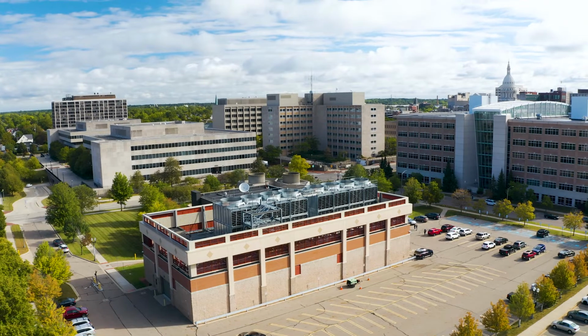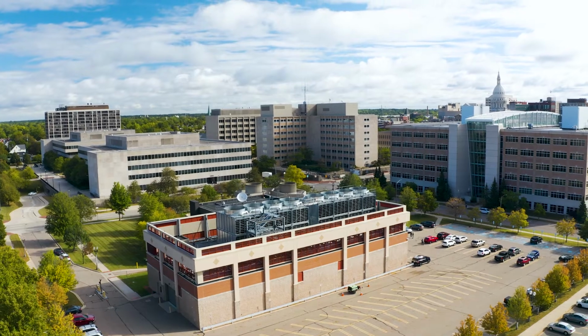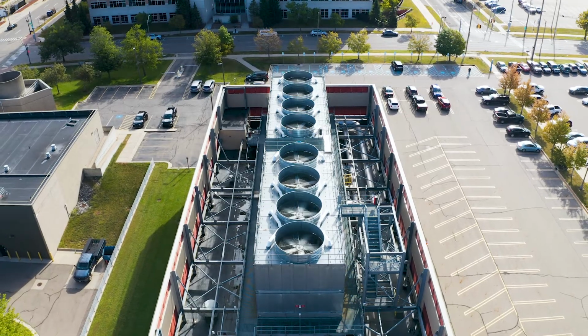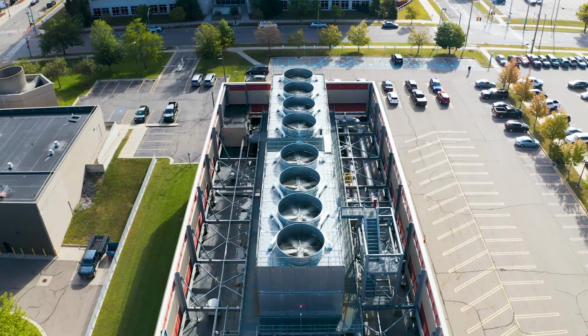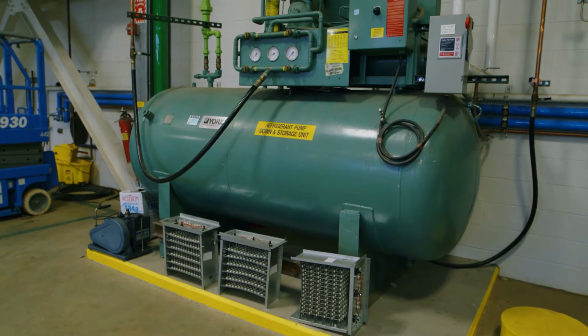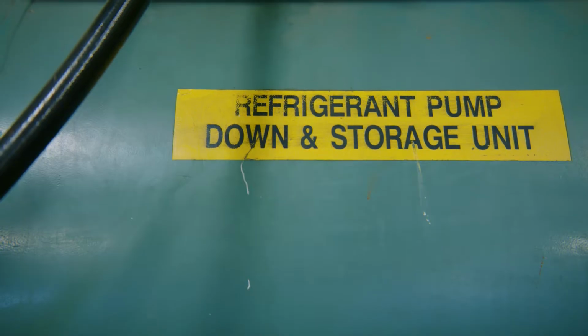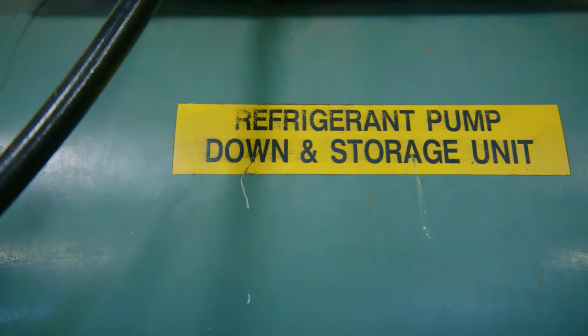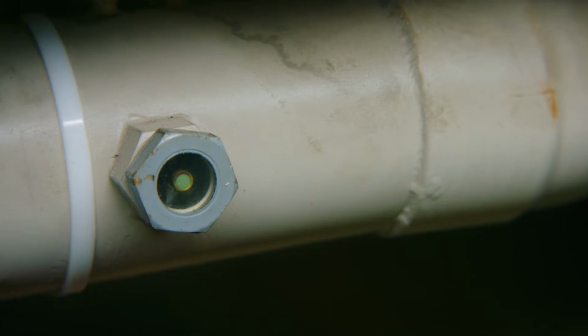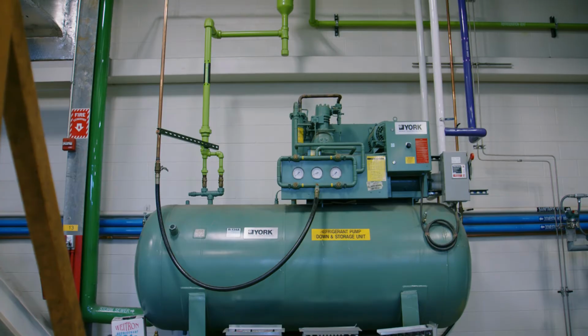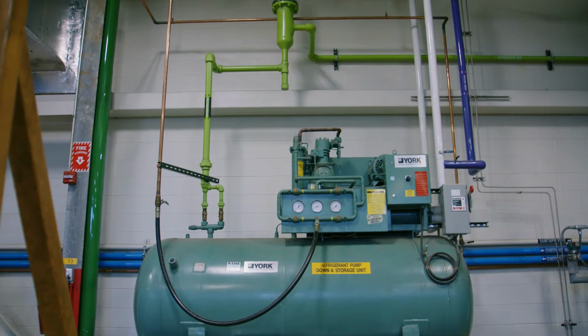The state-of-the-art four-story automated facility pipes water at 42 degrees Fahrenheit to downtown office buildings, used in place of building-mounted air conditioning units. What we do here at the Peffley Chilled Water Facility is just like your refrigerator at home. It chills one big giant box that cools the water down to go to our customers in downtown Lansing. And how we do this is we use refrigerant. Refrigerant goes across the tubes in a gaseous state, then in turn is turned back into a liquid, and this process continues until the chilled water is at optimum temperature to go back to our customers.